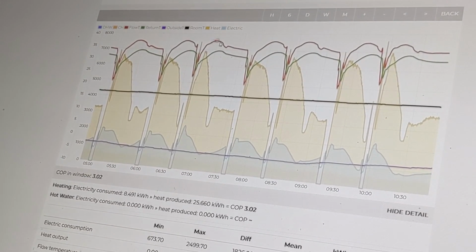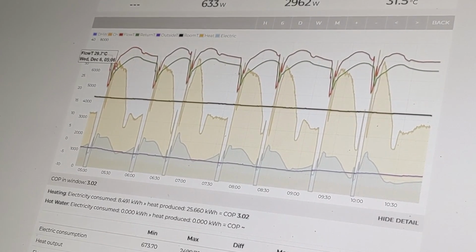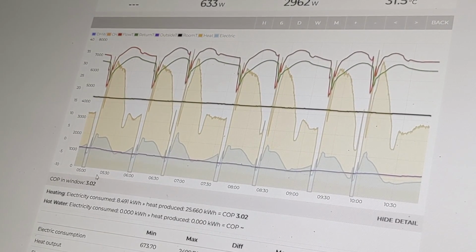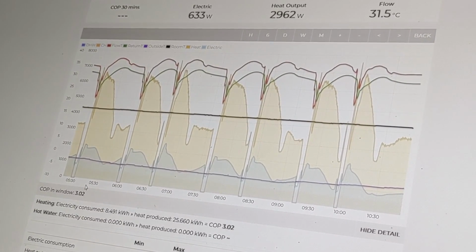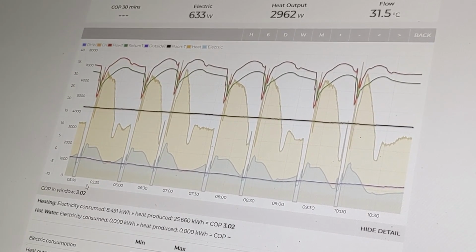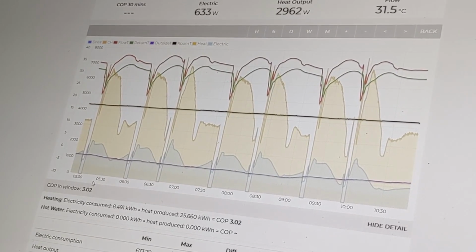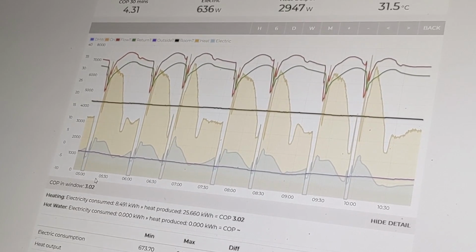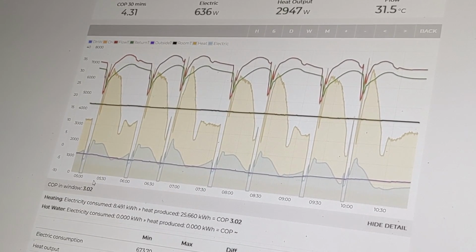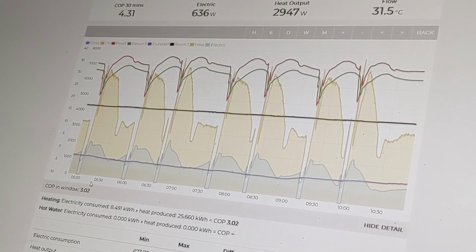Well, yes, I'm not entirely sure. We'd have to look at it in more detail. It could help him with his flow temperatures, which would then help with the coefficient of performance. A lot of the coefficient of performance is down to how low a temperature you need to heat your radiators up to. That's probably the single biggest factor: keeping the flow temperatures low, and that's influenced by good insulation and good size of radiators or heat output devices.